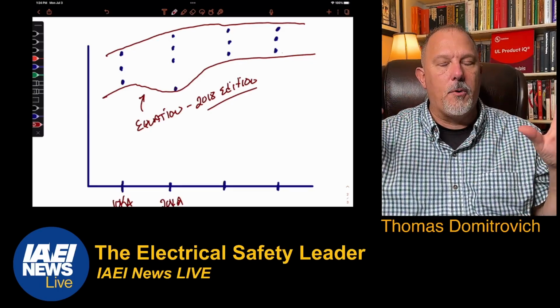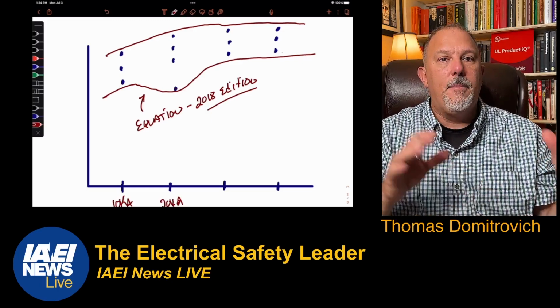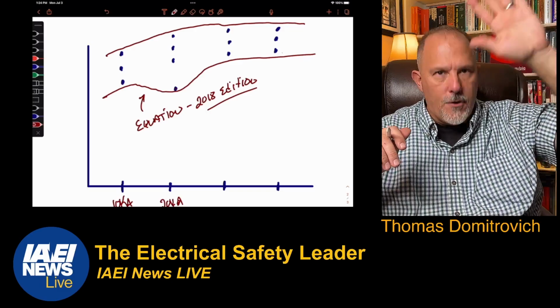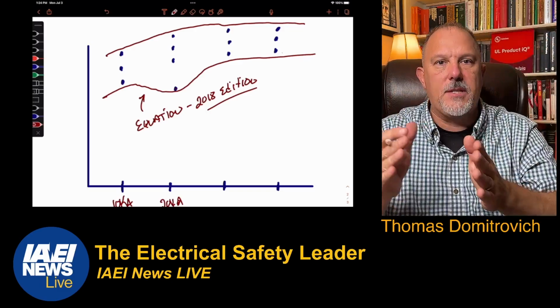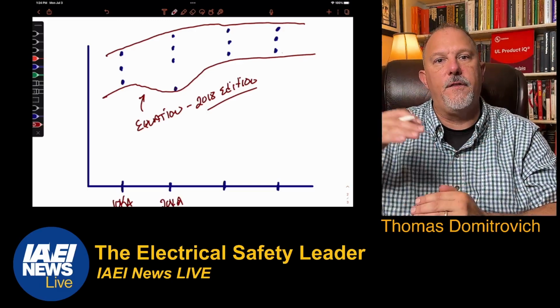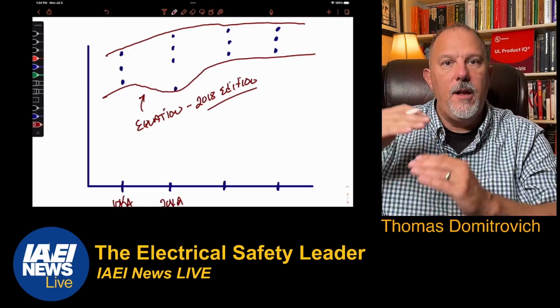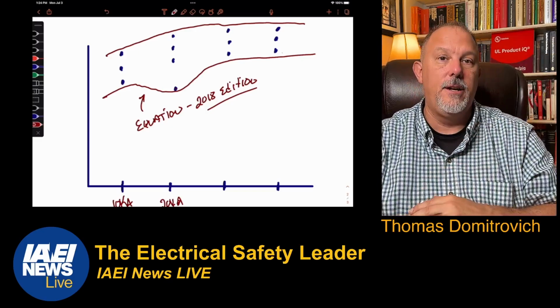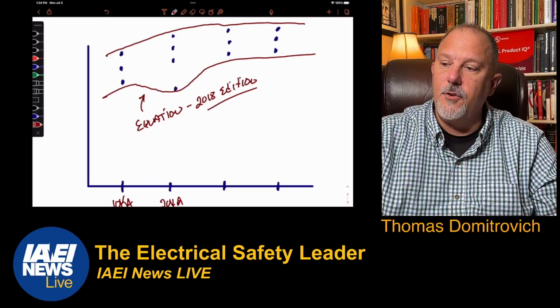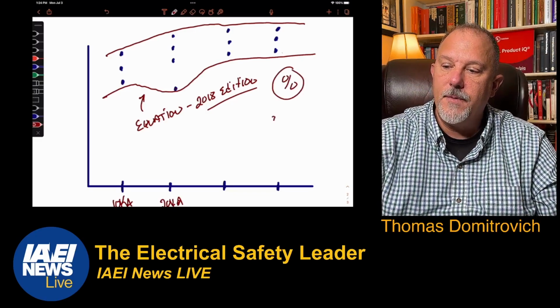Okay, so they added some more parameters to the 2018 edition that the 2002 did not have. But if you did the vertical bus, etc., and you made the gaps the same, the voltage the same, your minimum arcing current for the 2018 edition would be a higher number than the minimum arcing current for the 2002 edition of 1584. And it's because instead of using a blanket percentage, they went with an equation based upon the data. Okay, and that's significant if you calculate incident energy because, and I'll explain, you're going to see this in a minute, higher arcing currents can produce lower values of incident energy. So keep that in your mind, and we're going to get back to step 3.